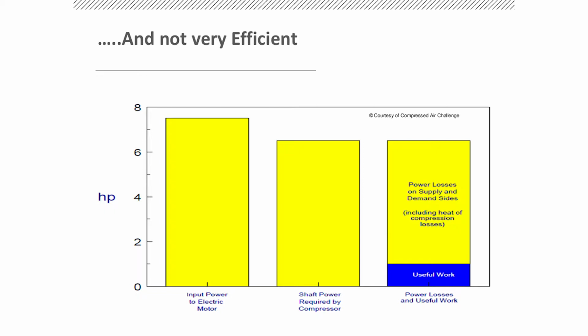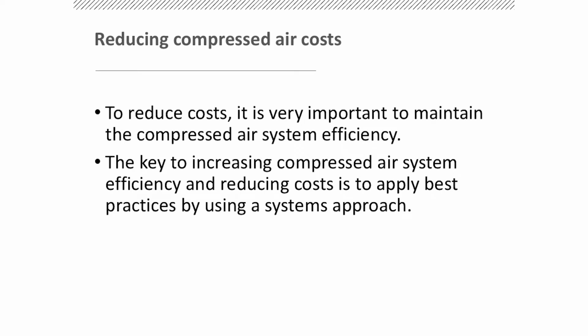The way this walks down is the 7.5 goes to about 6.5 for the losses through the motors and the drive and everything that goes into the compressor itself. Once you get into the compressor, you've got a lot of losses in heat of compression. As a matter of fact, they're terrible at making air, but boy are they good at heating. And the problem is you've got to get rid of that heat. And you will also find, if you're doing some retro-commissioning work, that if you've got compressors in a mechanical equipment room, they may not be getting enough heat out of there, and that's going to cause issues for other pieces of equipment in the system itself. So it's an important part to understand where the losses are.